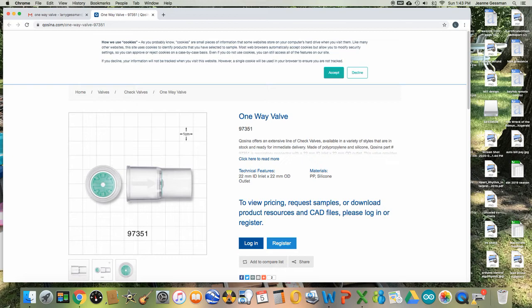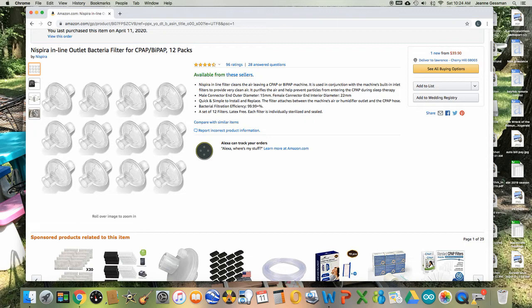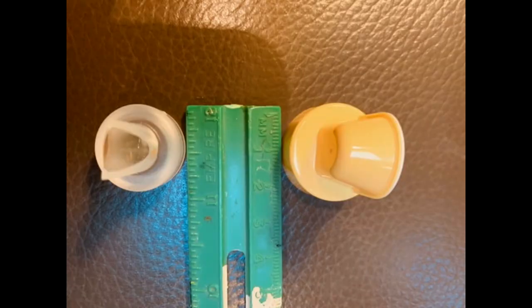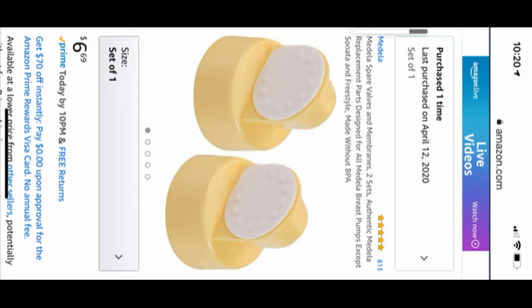When I went to the internet to try to find ventilator valves, they were easy to find, but when ordered I got a message by email the following day saying that orders were out of stock and would take many weeks, if at all, to receive delivery. So these items were basically impossible to get. To solve this problem, I ordered breast pump valves off the internet, which were promptly delivered from Amazon in one to three days. The remainder of this video shows how to use these valves in PVC piping to make the respiratory circuit necessary to prevent dead space in a simple ventilator.